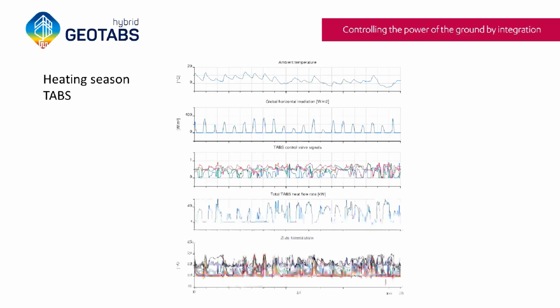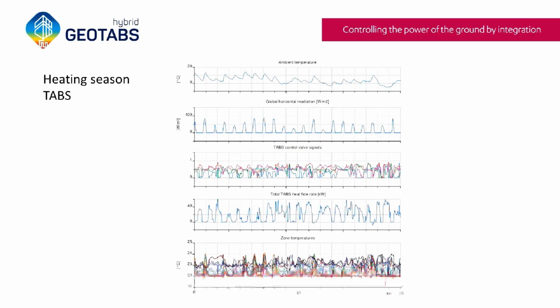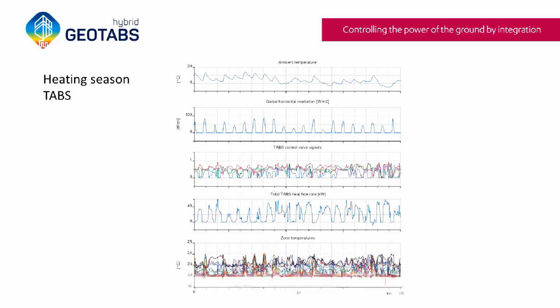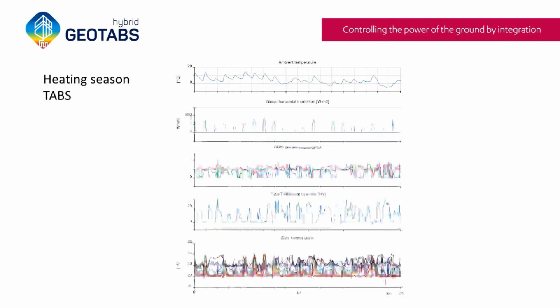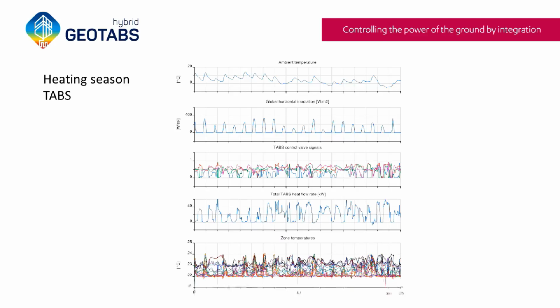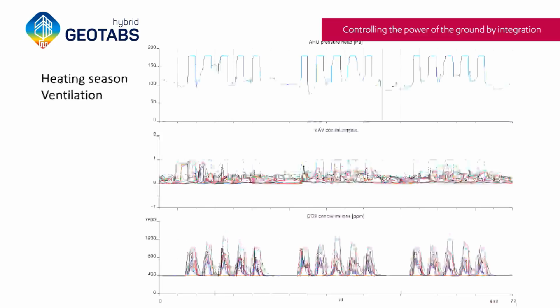These are all the zone temperatures, with an upper bound at 24 degrees, which is pretty much automatically satisfied by the heat dissipation of the building. This is different from classical building control, which typically uses an average outdoor temperature to control the heat flow rate and produces a more steady profile. The MPC uses its flexibility a lot more to heat efficiently.